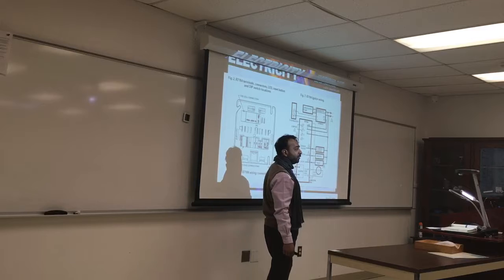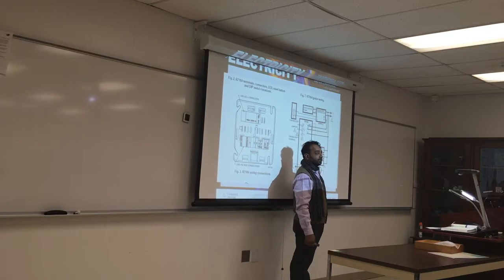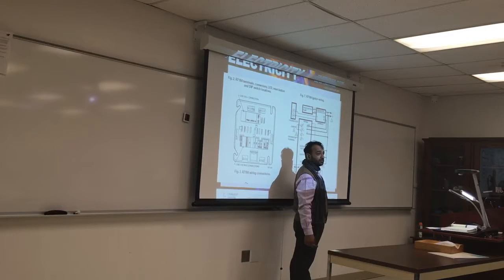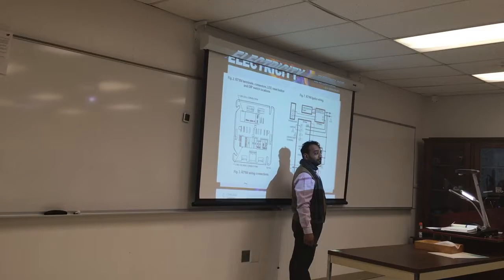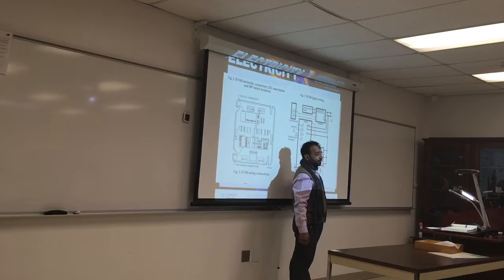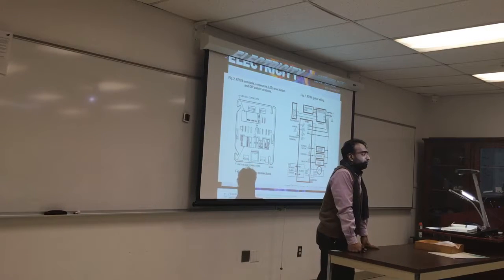So let's say you don't have aquastat and you want to power the primary control. What happens if you leave this one disconnected? Will it turn on? No, it's not going to turn on. It will think that aquastat is not requiring power. So what do you do? This says I have a system that has no aquastat and the control requires a limit. What should I connect to that limit?